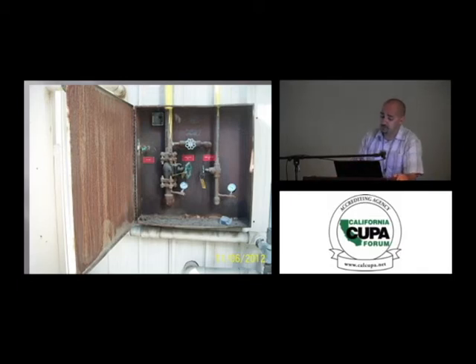This one here in particular, I opened it up and realized that, of course, all the proper labeling was not there. But if you look carefully, it's hard to tell in this picture, the equalizer line does not tie from the high side to the low side. It has a 90 and it turned back inside to the compressor room. I got into the compressor room, tracing that line, and it was capped off. Why it was capped off, I don't know.